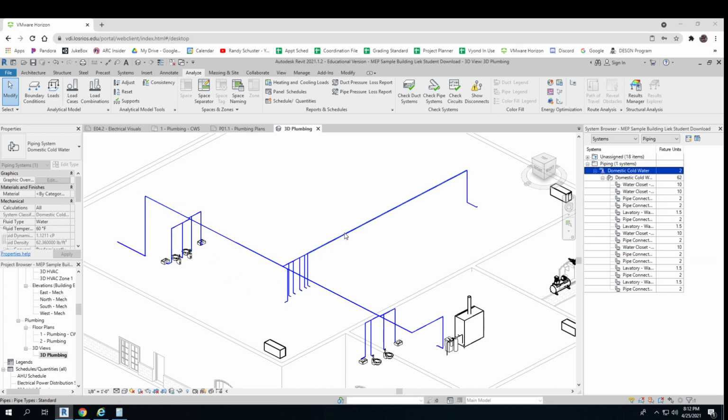These ones, if they're not all turned on at once, the water will come here and then it'll flow down this way. And by the time all of these are turned on and this one goes, it's going a fairly long way. And that could be of interest to us. And we'd have to calculate the friction all that way with everything being on and see what happens. But the one that's probably the most concerning, these flushometers and valves on the lavatories really make for a heavy duty friction loss, and it's a long way to go.